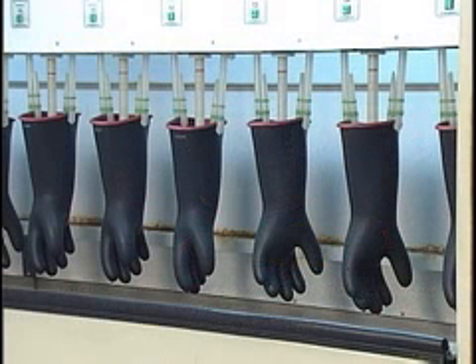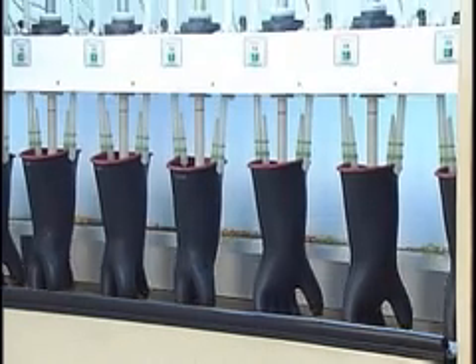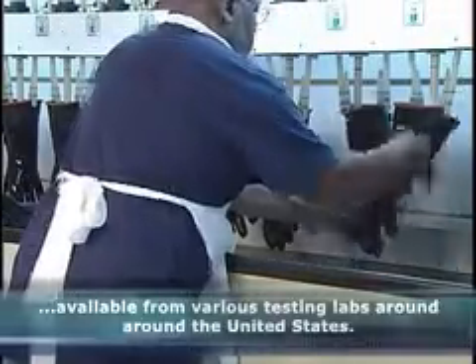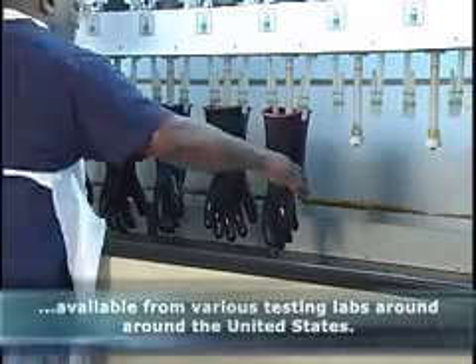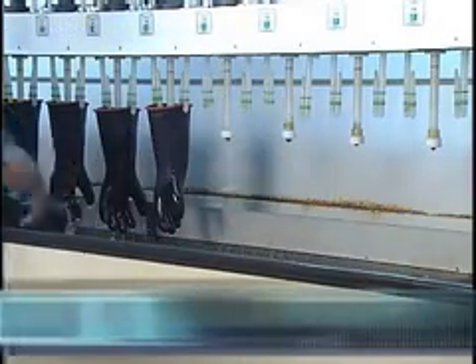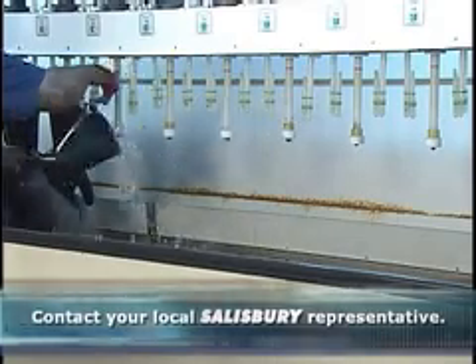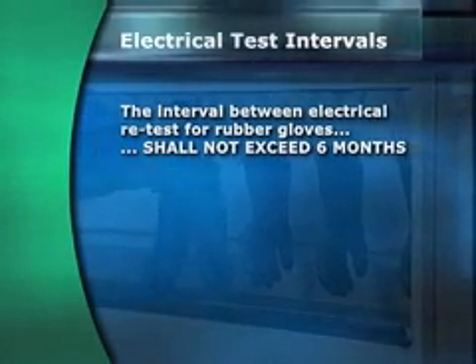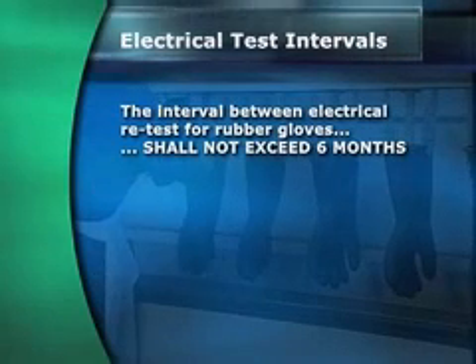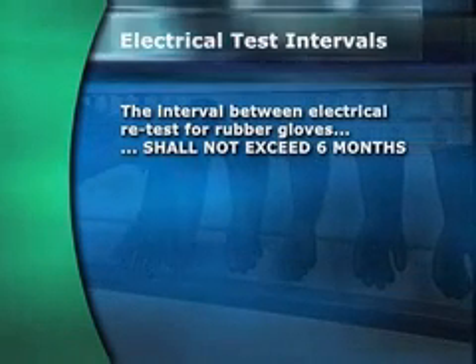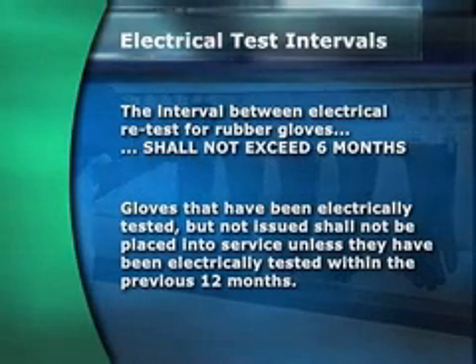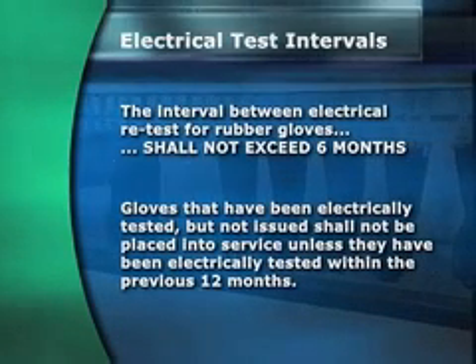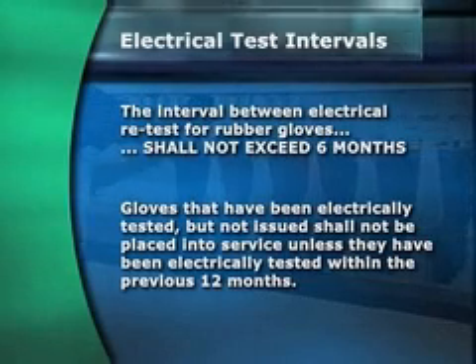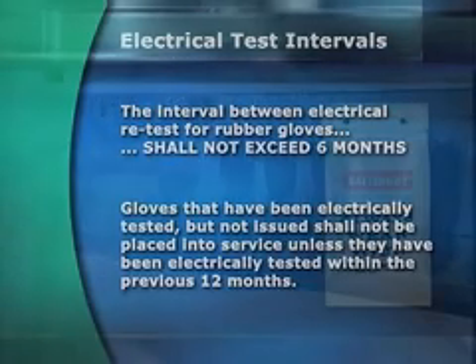The other vital part of field safety is periodic electrical testing of rubber insulating gloves. This is done on highly specialized equipment, which is available from various independent testing laboratories around the United States. For information on a test lab near you, contact your local Salisbury representative. The interval between electrical retest for rubber gloves, in other words, gloves issued for service, shall not exceed 6 months. Gloves that have been electrically tested but not issued shall not be placed into service unless they have been electrically tested within the previous 12 months.